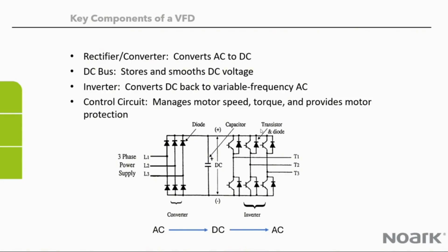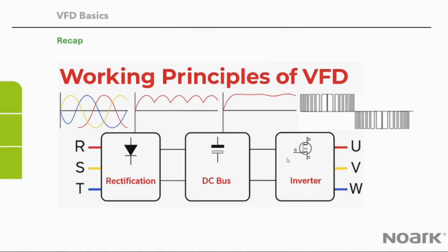And then this section out here is called the inverter. These are the transistors that are also commonly known as IGBTs. They are utilized to fire the bus voltage, which is a DC voltage, on and off to the motor. And how we vary that on and off sequence controls the speed that goes to the motor and makes the motor run at different speeds.